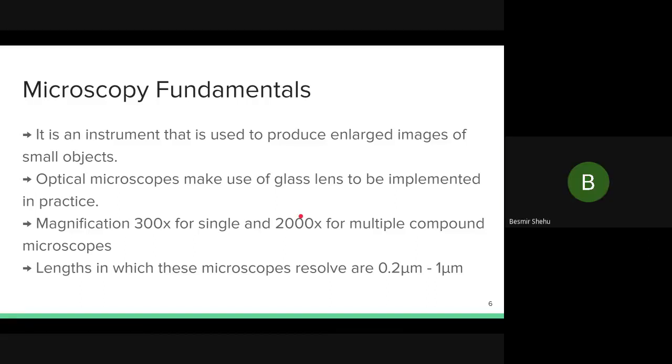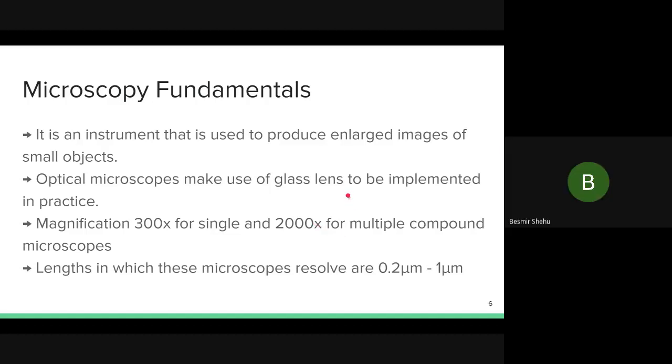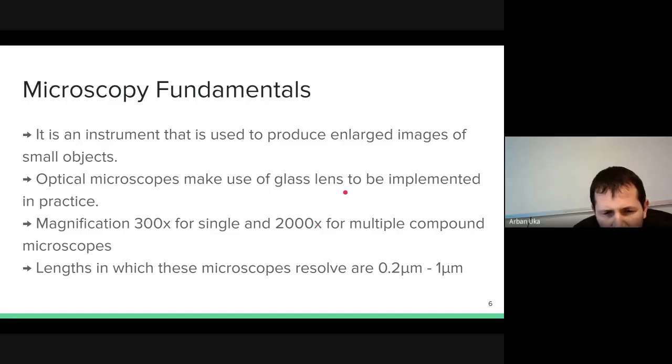It is big enough for the naked eye to see, because the light goes from the condenser into the objective, and then we can see them in a digital manner or by looking at the objective lens. Okay, so 1 micrometer times 2,000 is 2 millimeters, right? Yeah, 2 millimeters. Then this 2 millimeters will go onto the camera.